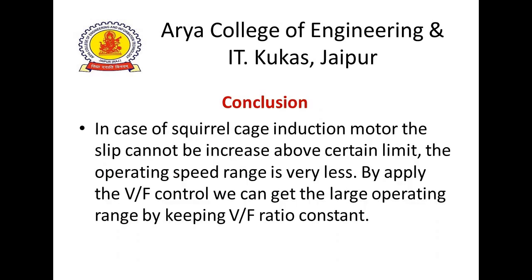In the case of a squirrel cage induction motor, the slip cannot be increased above a certain limit, so the operating speed range is very small. By applying voltage and frequency control, we can get a large operating range by keeping the voltage and frequency ratio constant. So I have explained the methods of speed control of induction motor.